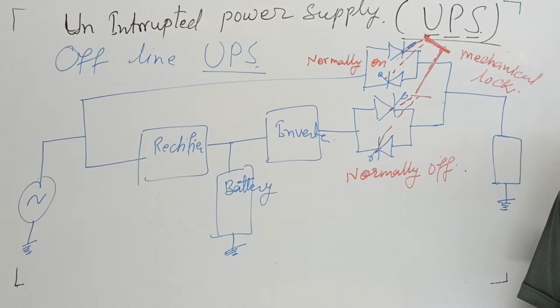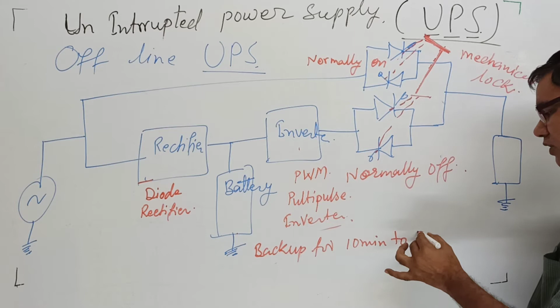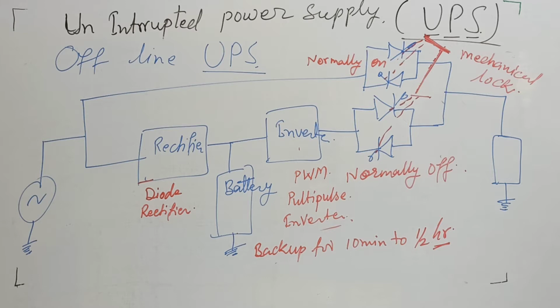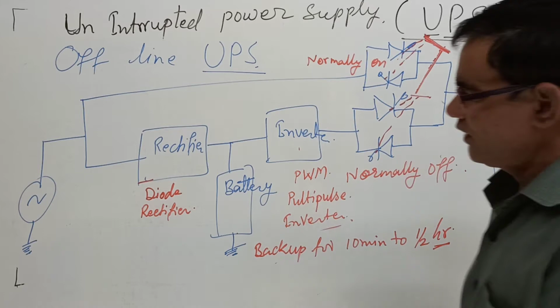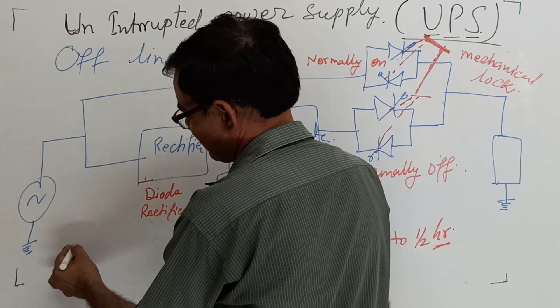What happens in the offline UPS? It has a simple diode-based rectifier, a diode rectifier. It has a simple PWM, multi-pulse inverter. It has backup for 10 minutes to half an hour, not more than that. The rating is 500 VA, 1 kVA, 2 kVA, like this.